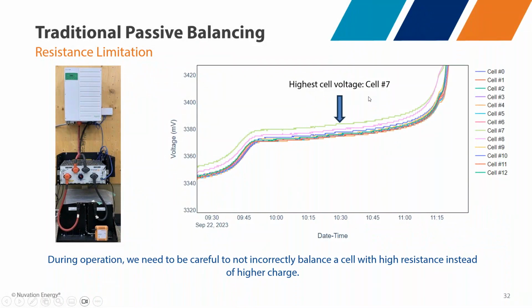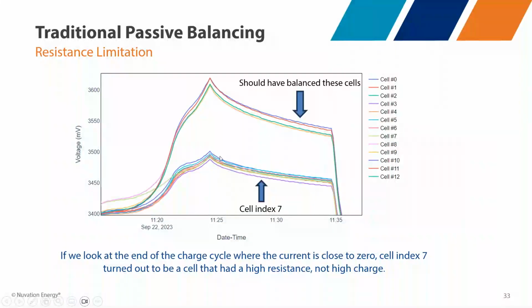In traditional passive balancing, this is one of the gotchas you have to be careful about. If you look at this system, this green cell, cell number 7, has the highest cell voltage. So if one used just voltage-based passive cell balancing, it would look like you need to balance down cell 7. However, you need to be careful that it's actually a higher state of charge per cell rather than a higher resistance. So in that same stack, as we get to the end of the charge cycle and current limit down to a low charge current, cell index 7 is now buried in this group here—it actually was not at a higher state of charge. It's actually these other cells over here that should have been balanced down. This is one of the things to pay attention to when doing voltage-based balancing.